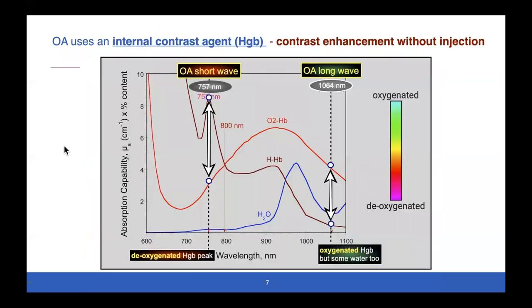We use two different wavelengths, though you don't need to remember the numbers. The short wave is colored red because we code deoxygenated blood as red, and the long wave is color coded green because that's absorbed primarily in oxygenated blood. We chose these wavelengths to get the maximum difference between oxygenated and deoxygenated blood, and also to avoid the confounding water peak.